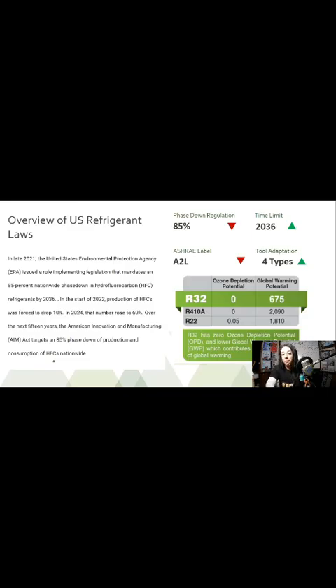We've already done that. However, if you look at the global warming potential of R22, it was actually less harmful to the warming effect, to the greenhouse gas effect than 410A. So what we got rid of with the chlorine, we gained with the global warming potential. So now we're like, crap, we've got to deal with that because now we're warming the atmosphere. So what do we do? We take half of 410A. That's right, folks, half of 410A. It's 410A without any flame suppressant. And we take that and we use it as a refrigerant. So we have 0 ozone depletion potential now and only 675 GWP. That is absolutely beautiful compared to what we have done for the last 100 years.